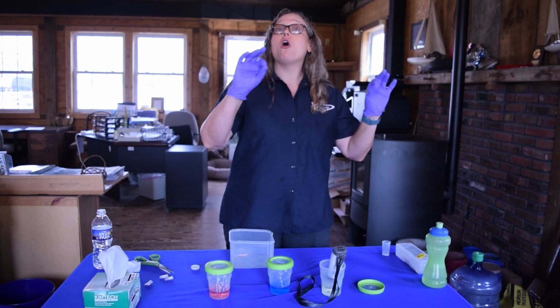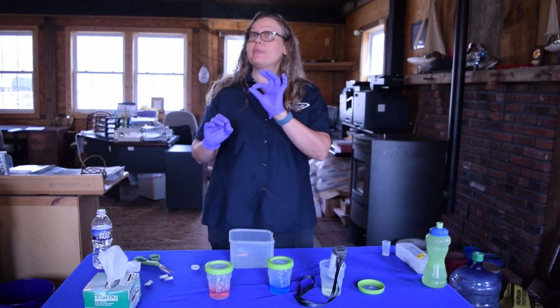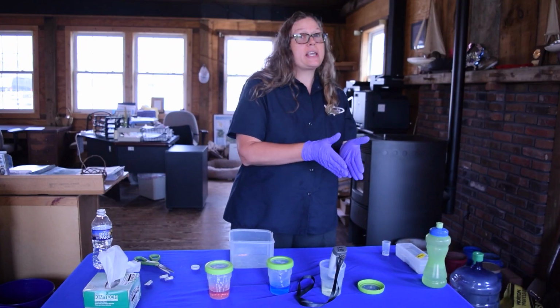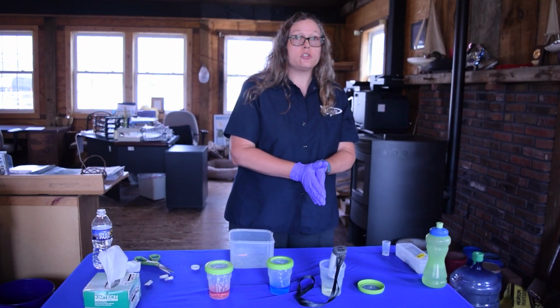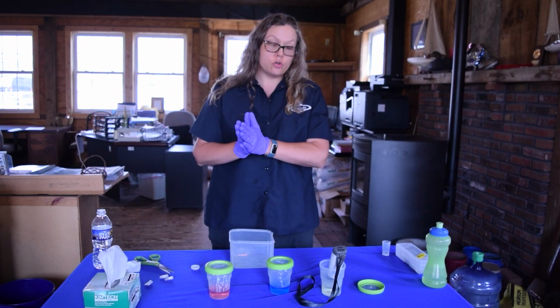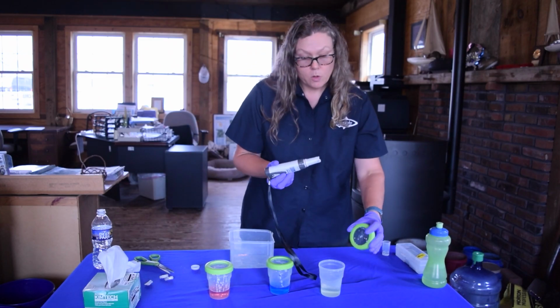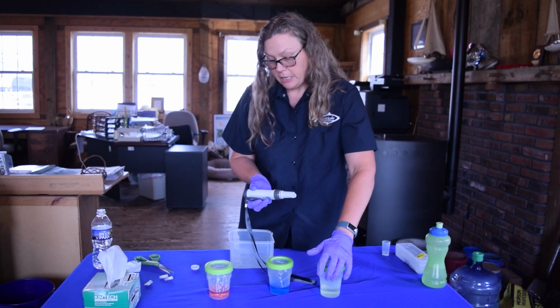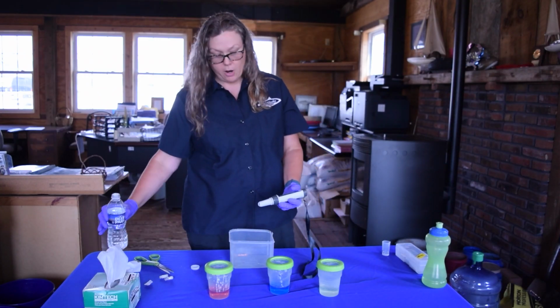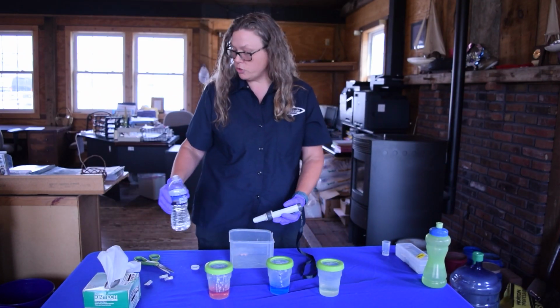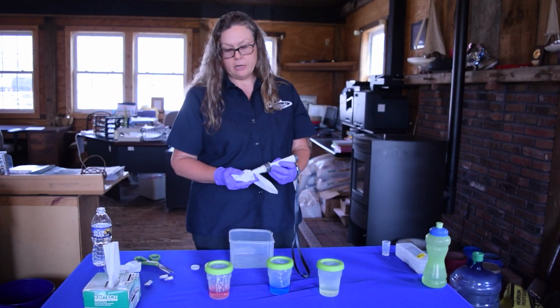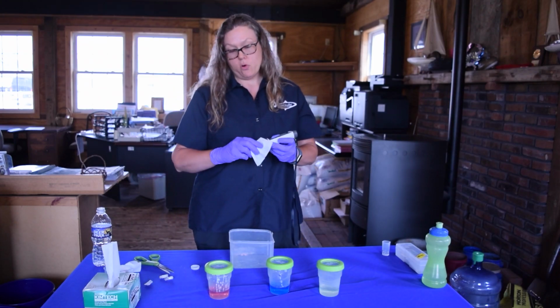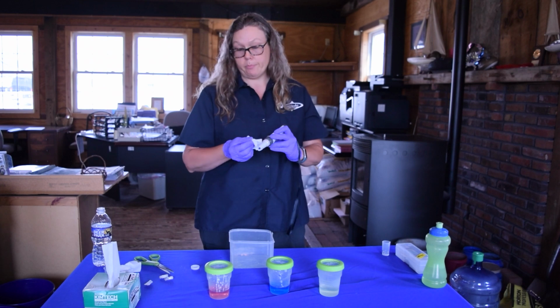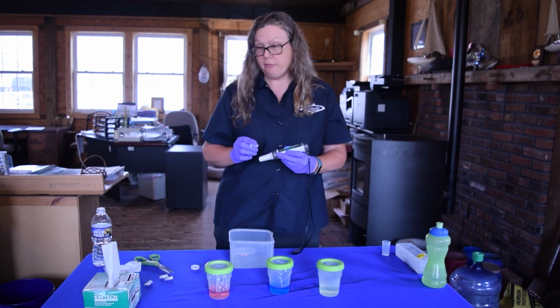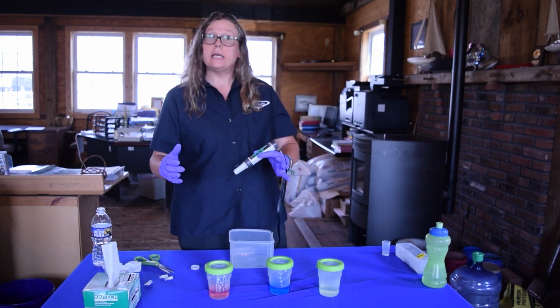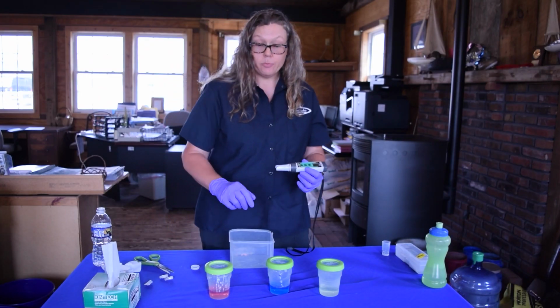If you're seeing all 3, the L, the M, and the H, that means that you did not just calibrate your pH. So that is something really important to look at. At this time, we can now remove the pH meter from the 7.0 solution. We're going to do a quick rinse and another wipe. And it's really important that we always rinse and wipe the pH meter before and after taking a reading or going through a calibration point.